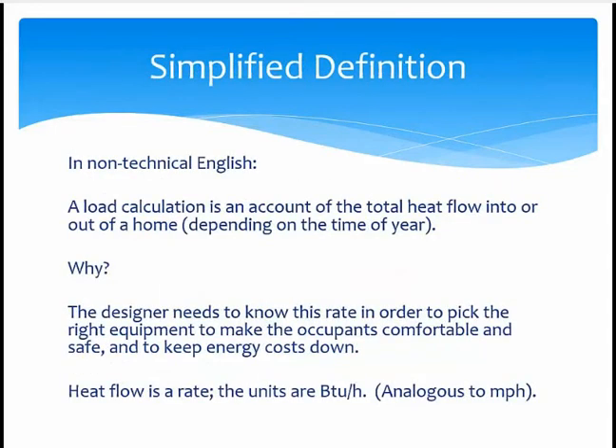Here's a simpler explanation. Load calculation is really just an account of the total heat flow into or out of our home, depending on the time of the year. The reason we need to do one is so that the designer knows the rate of heat flow so that they can pick the right equipment that makes the occupants comfortable and safe, but also keeps energy costs down. Note that heat flow is a rate and has a unit of BTUH, which stands for British Thermal Units per hour.